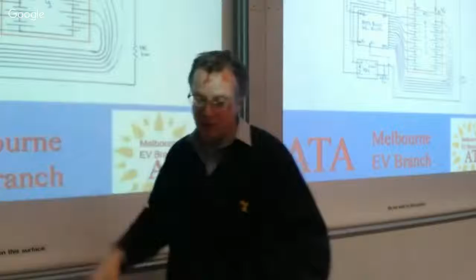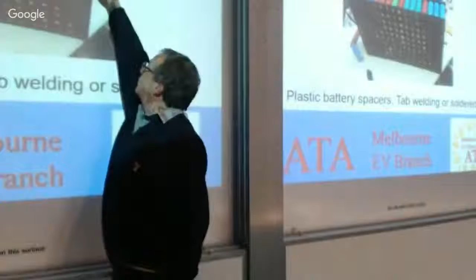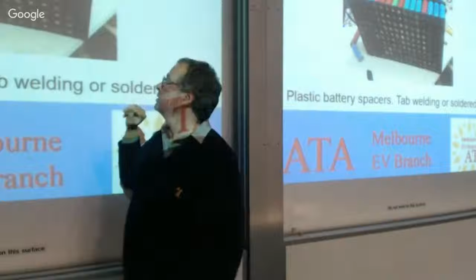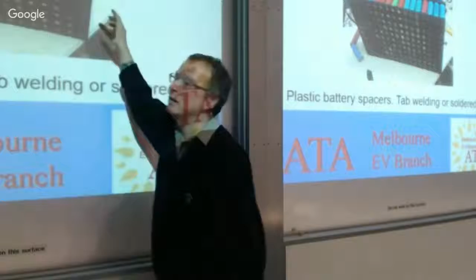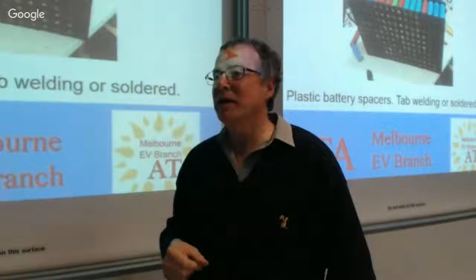So say this block is 70 ampere hour instead of 80. What you do is add a few more cells on the end. You can use these tab joiners, or bands, clipping a few more onto the other side to add to that bank of cells, adding sufficient cells to bring it back up to 80 ampere hour.